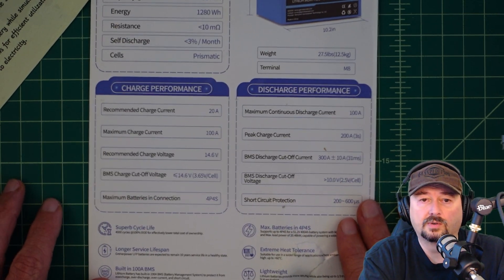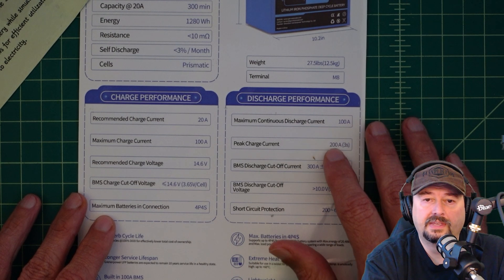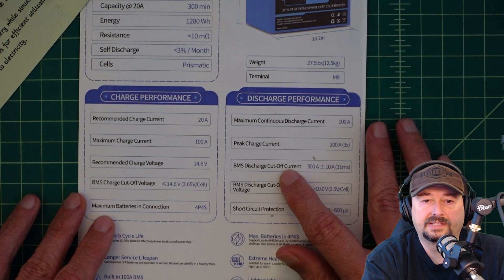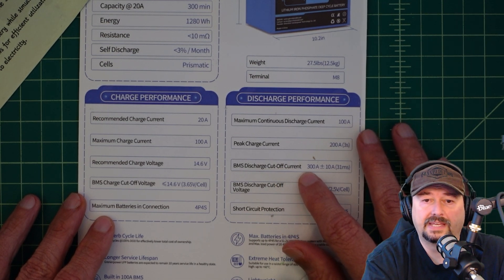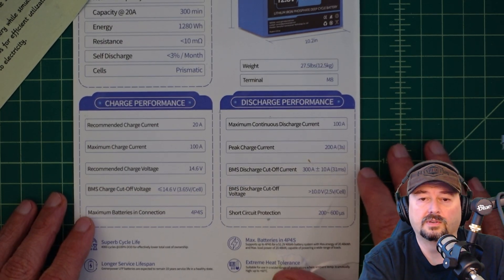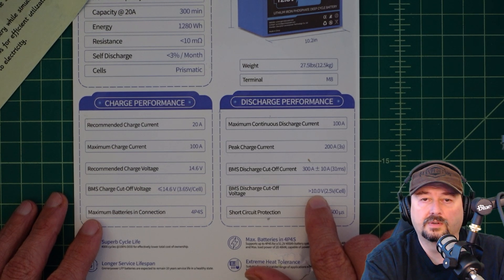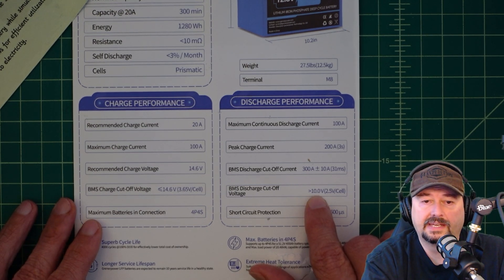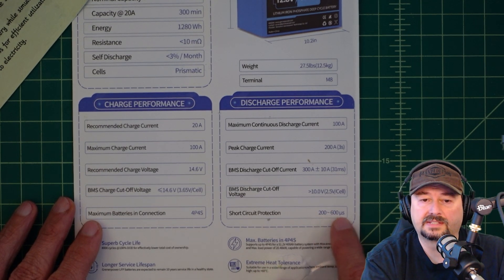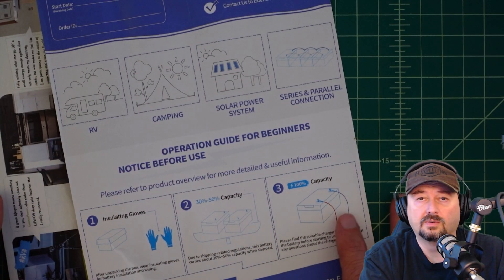Maximum batteries in connection is four parallel, four series — so that would be 16 batteries in total. For discharge performance, maximum continuous discharge current is 100 amps. Peak is 200 amps at 3 seconds. BMS discharge cutoff current is 300 amps plus or minus 10 amps at 31 milliseconds — that's for surge draws or loads. BMS discharge cutoff voltage is 10 volts, which is what we'll run our capacity test at. Short circuit protection is 200 to 600 microseconds. The instructions are a little limited, but there may be more detail on the website.